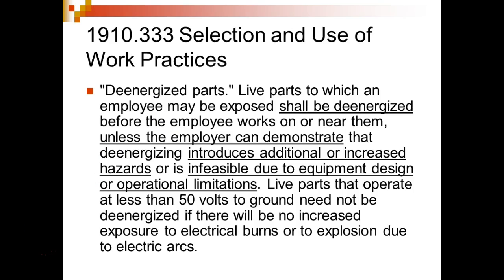De-energized parts: live parts to which an employee may be exposed shall be de-energized before the employee works on or near them, unless the employer can demonstrate that de-energizing introduces additional or increased hazards, or is infeasible due to equipment design or operational limitations. Live parts that operate at less than 50 volts to ground need not be de-energized if there will be no increased exposure to electrical burns or explosion due to electrical arcs.